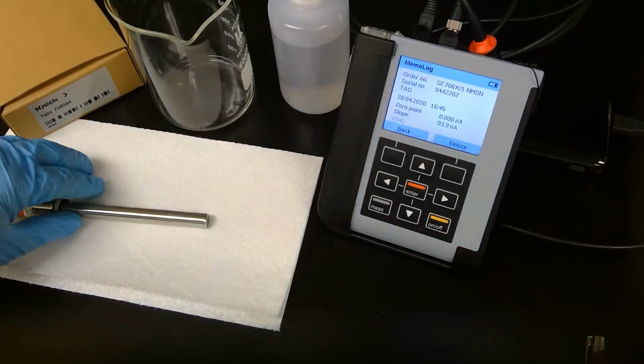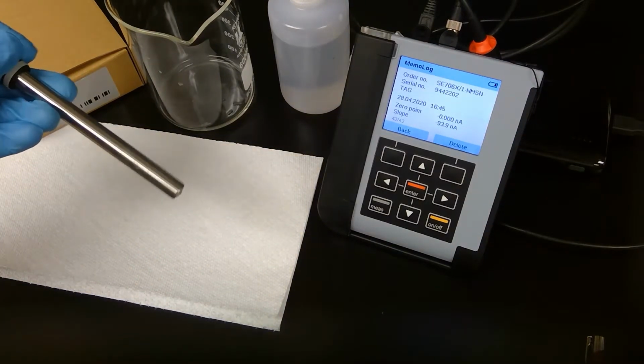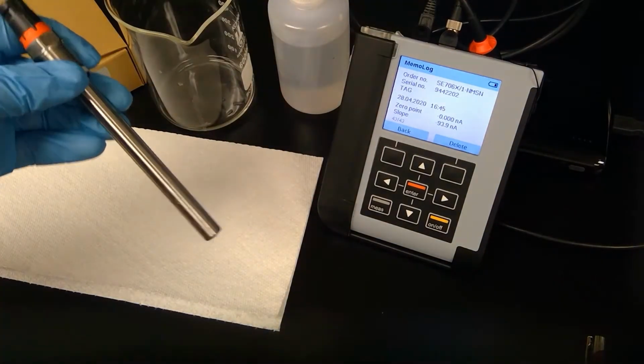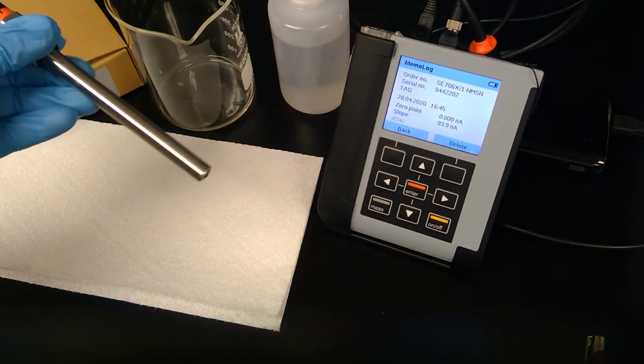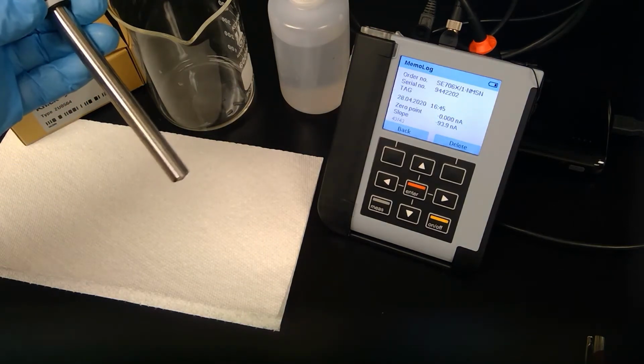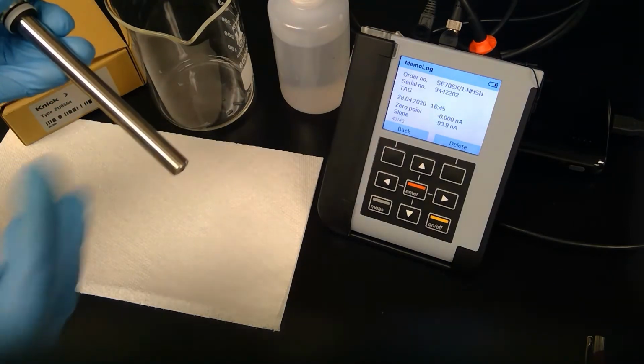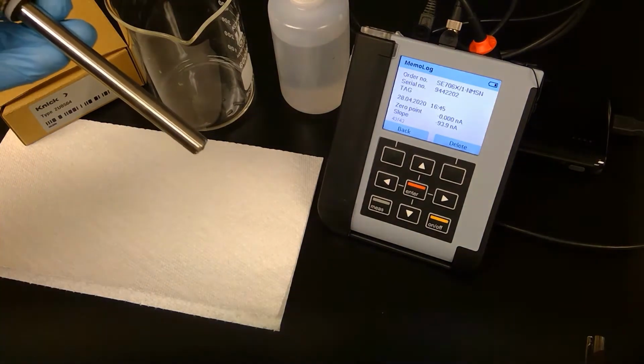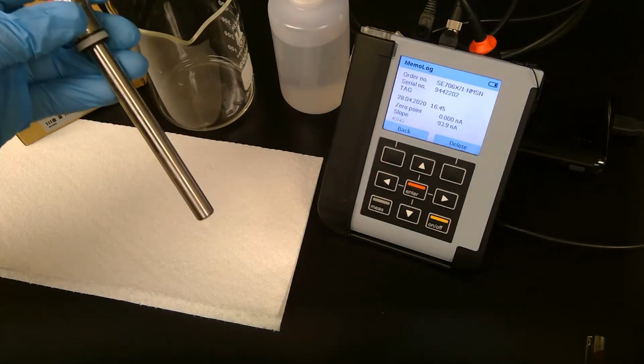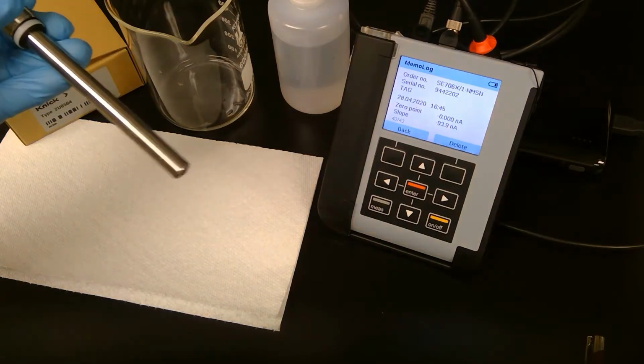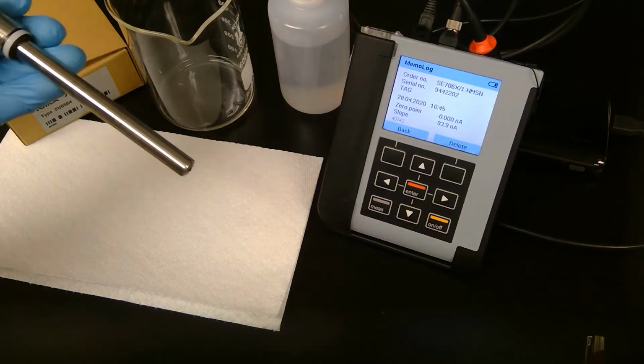Today what we're going to do is a PM on this SE706 amperometric Clark cell sensor, dissolved oxygen electrode. What that's going to look like is we're going to replace the membrane and refill or replace the electrolyte to get this back up and working. So it's a pretty straightforward thing.